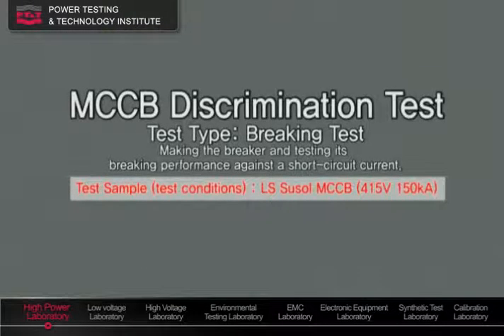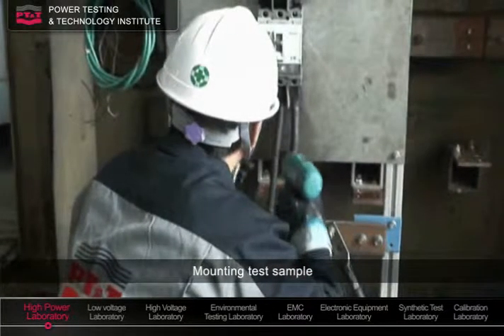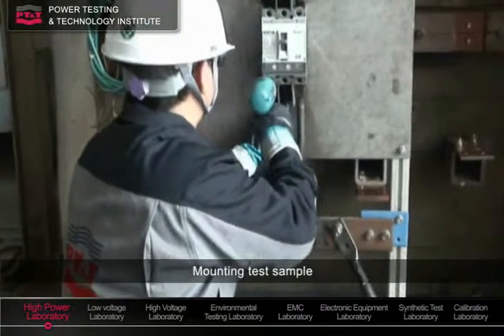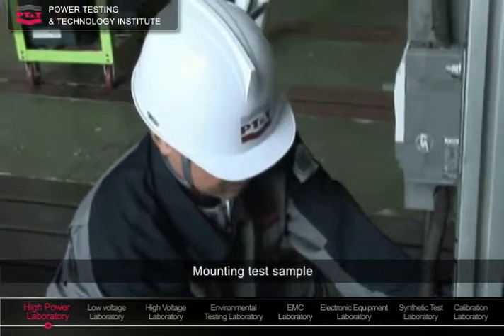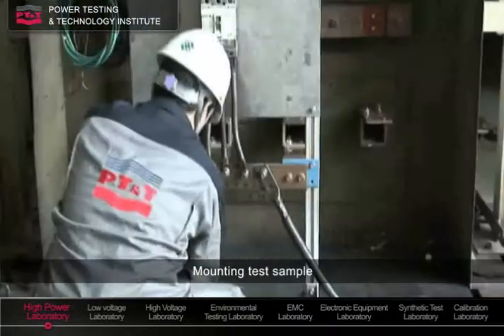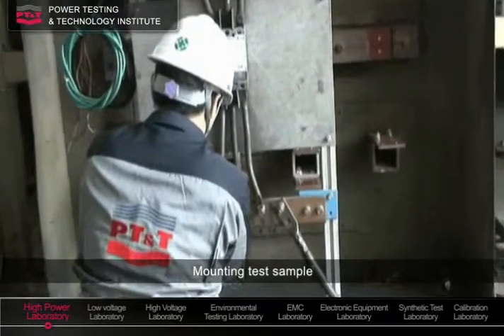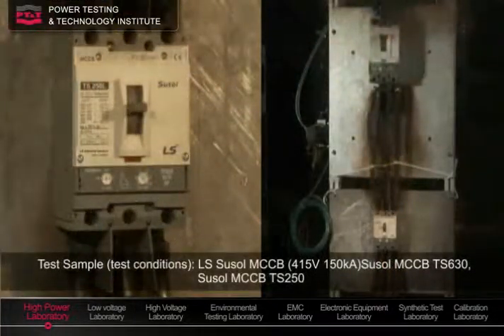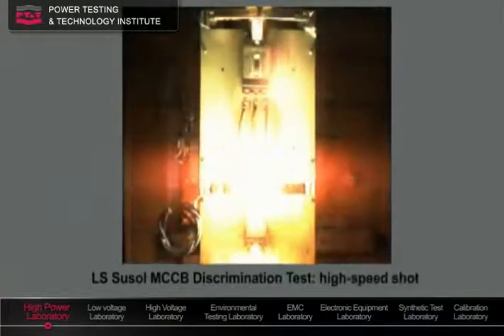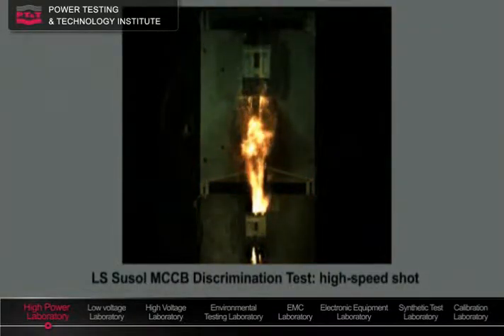This is a successful case of an MCC-B discrimination test. Discrimination tests are conducted to verify the backup breaking performance of MCCBs. In this test, only the sub-breaker directly related with the fault circuit should be tripped, while the top-breaker is not tripped to secure power supply to other healthy circuits. As you can see, only the sub-breaker was tripped to prove its reliability and ability of discriminating operation.